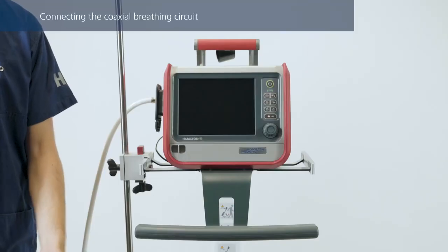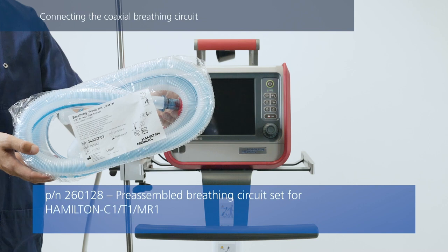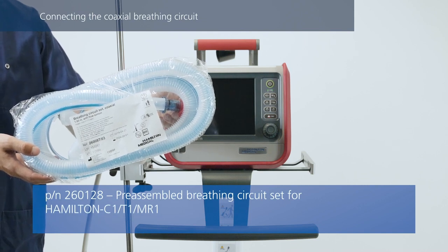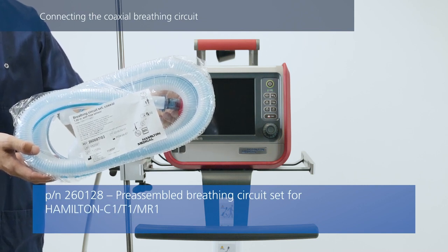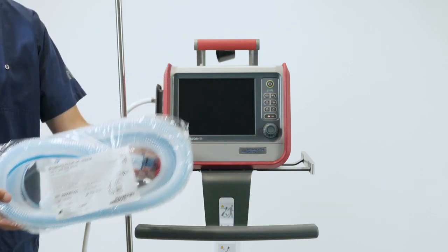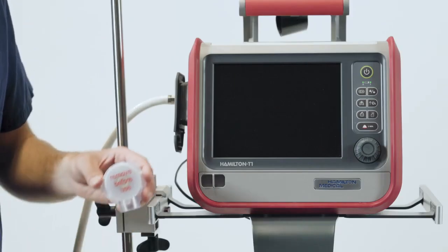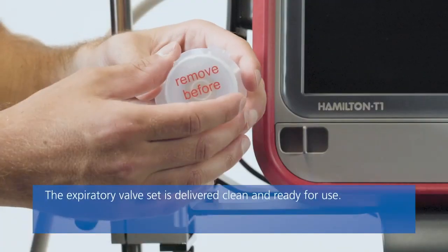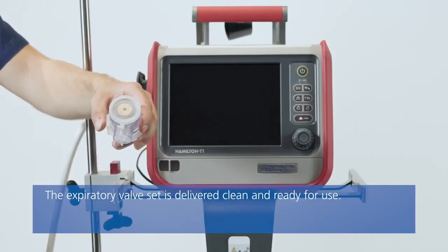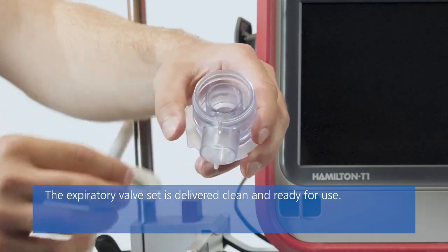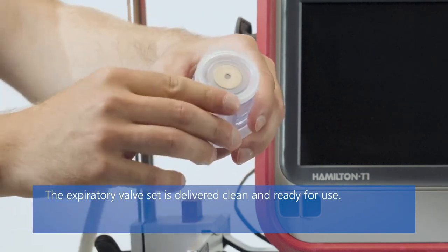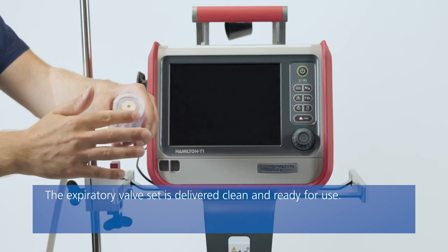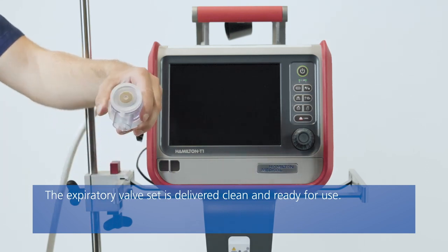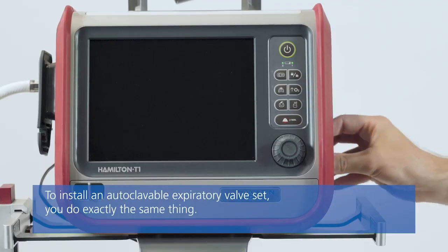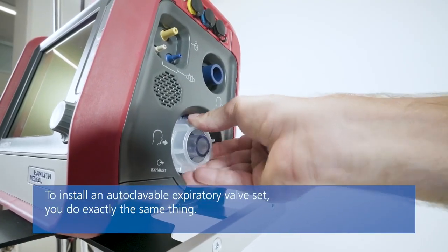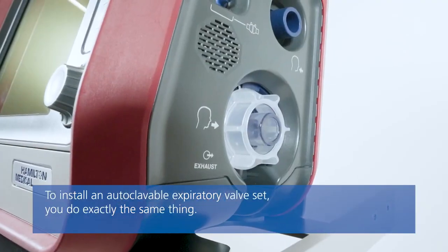If you are using a pre-assembled coaxial breathing circuit, this contains everything you need, namely the expiratory valve set, the breathing circuit, and the flow sensor. Be sure to check the expiratory valve set before using it on the patient. Firstly, remove the safety cover. And check that the membrane is properly aligned with the expiratory valve housing, and the metal plate is facing upwards. Position the expiratory valve set in the expiratory port and twist it clockwise until it locks into place.